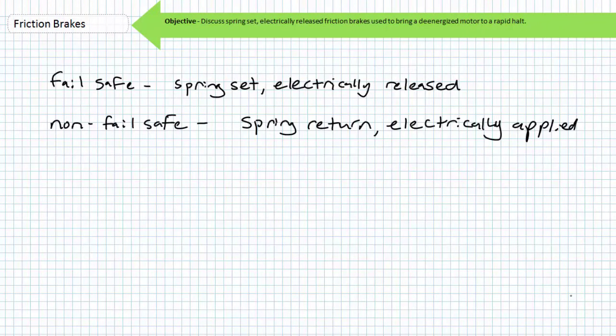Friction brakes come with two different designations and their description says it all. Fail-safe brakes require power to disengage the brake. Otherwise, spring pressure applies the brakes. Fail-safe brakes are also called spring-set electrically-released brakes. They're additionally known as power-off or safety brakes. Non-fail-safe brakes require power to apply the brake. Otherwise, spring pressure disengages the brakes. Non-fail-safe brakes are also called spring-return electrically-set brakes. They're additionally known as power-on brakes.